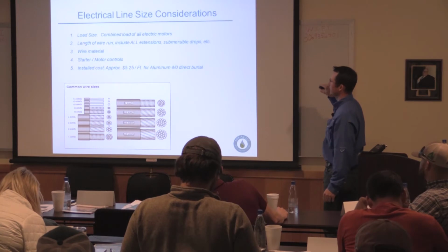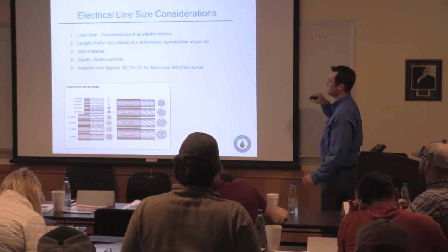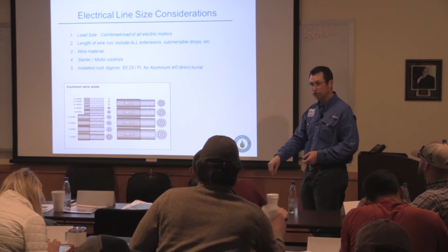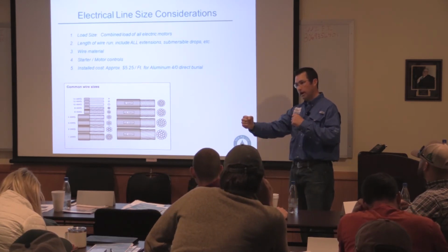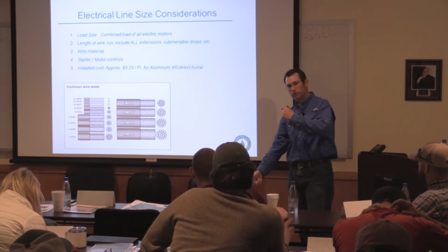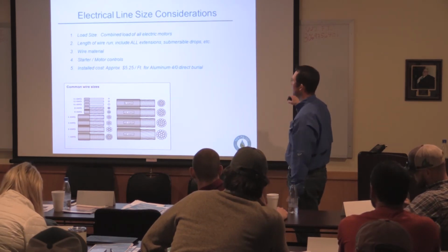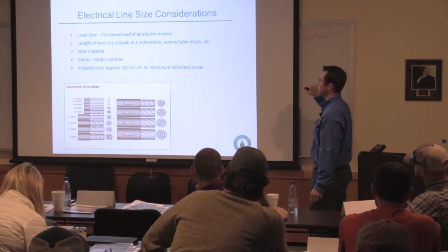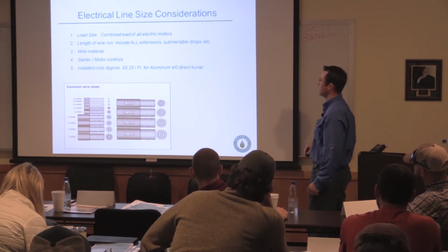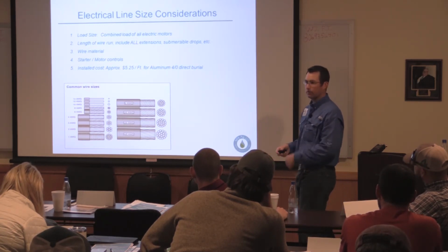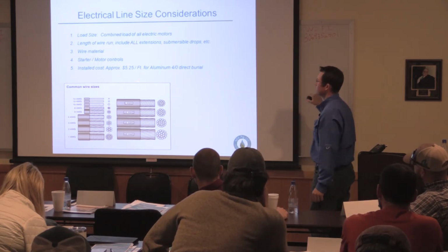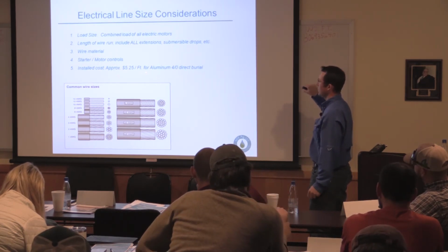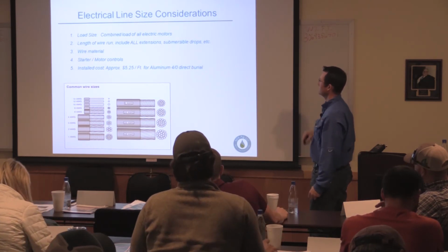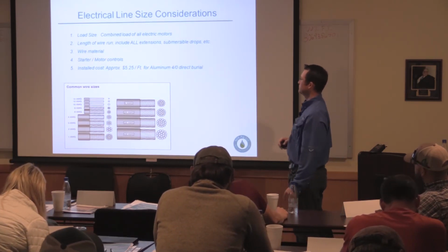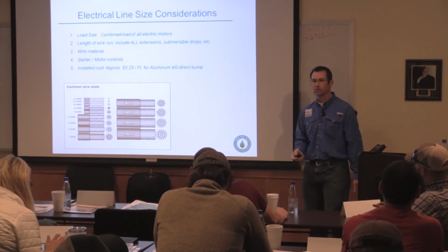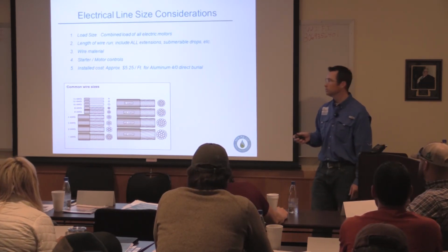Another consideration you have to have is the length of wire on the run, which includes all the extensions. The submersible drops is part of that as well. Remember that submersible, just getting power to the top of the ground is one thing. You've got to get power all the way down to the motor and the hole to make it really efficacious for you. You're looking at your wire material, which makes a difference. Your starter and motor controls, going back to if you've got something that's going to be across the line, you're going to have bigger wire sizing to accommodate for that. And then the summary here is the installed cost of 4/0 direct burial aluminum is about $5.25 per foot trenched and installed. That's something you can budget towards.